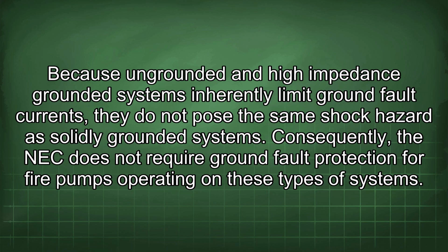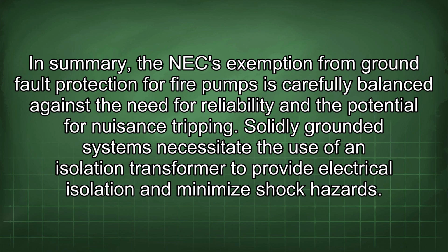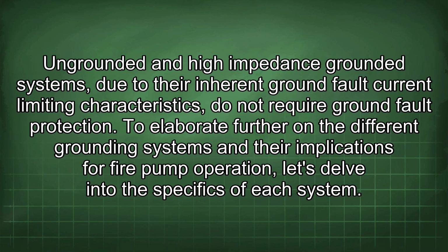of systems. In summary, the NEC exemption from ground fault protection for fire pumps is carefully balanced against the need for reliability and the potential for nuisance tripping. Solidly grounded systems necessitate the use of an isolation transformer to provide electrical isolation and minimize shock hazards. Ungrounded and high impedance grounded systems, due to their inherent ground fault current limiting characteristics, do not require ground fault protection.